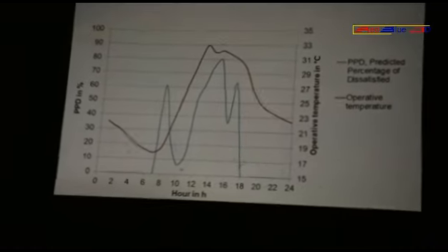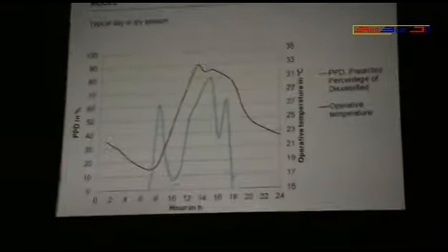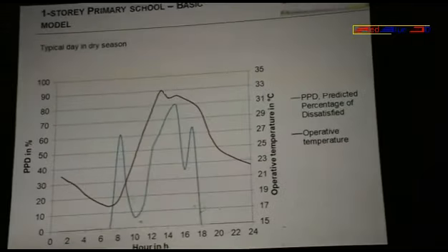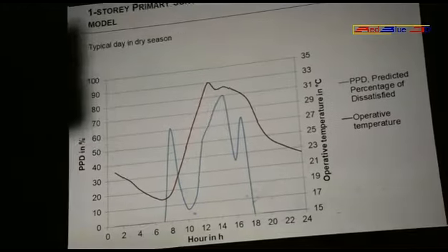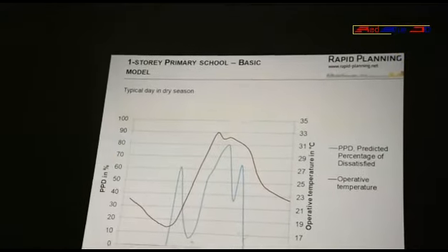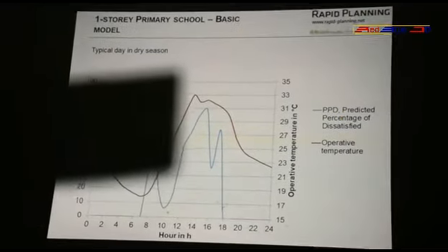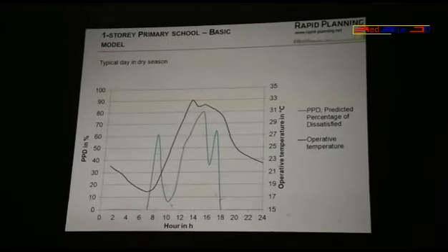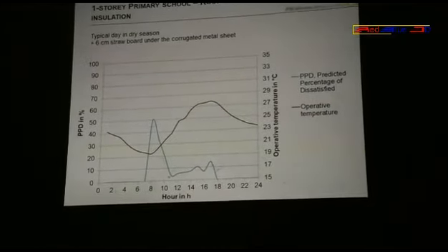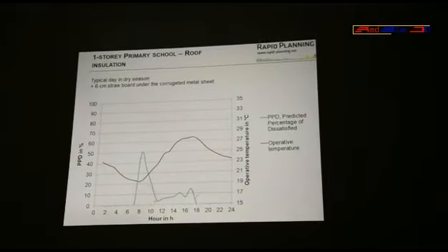We take a special look at one day in the dry season, since it has the highest temperature difference between night and day. We show both the temperature in red and the PPD in blue. In the morning, people are dissatisfied at around 60% because it's too cold at 18 degrees. Then the temperature rises and the PPD goes down until about 10 a.m. After that, it rises again and we have a problem of overheating — people are dissatisfied because the temperature is too high. We again added a straw panel in the roof and fixed the overheating problem during the afternoon.